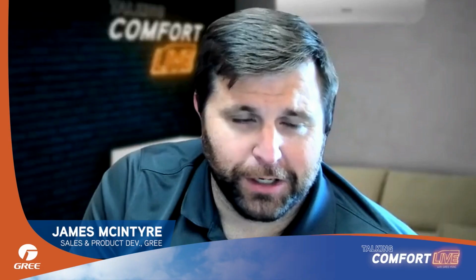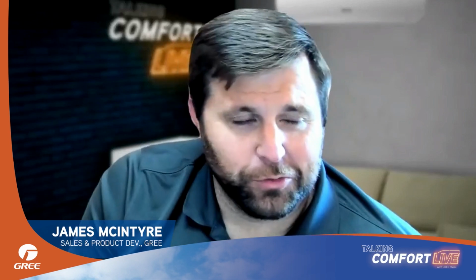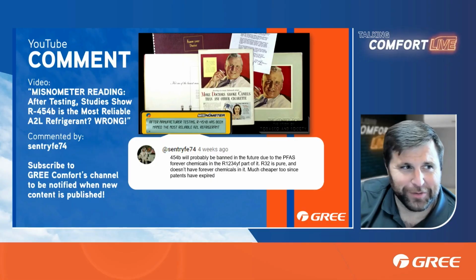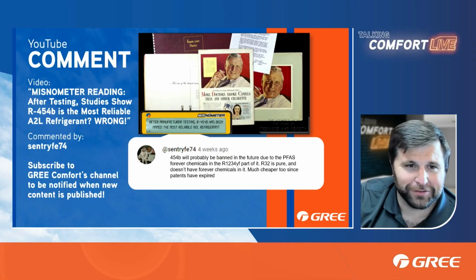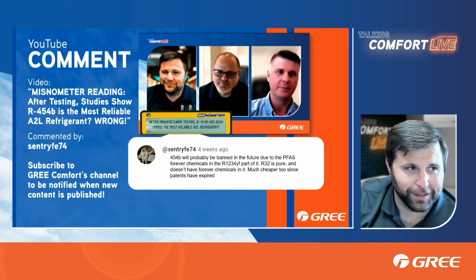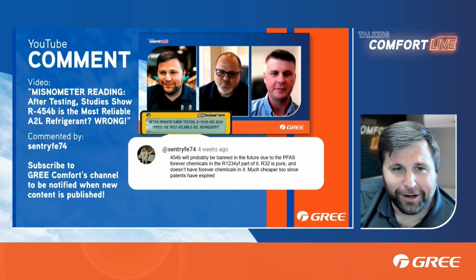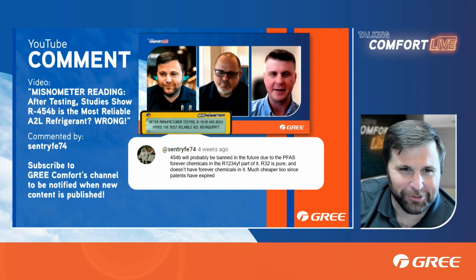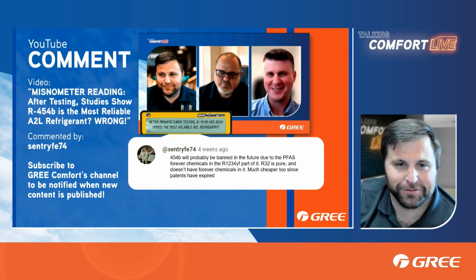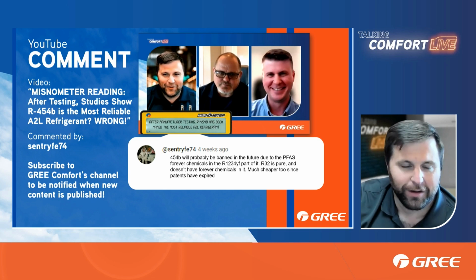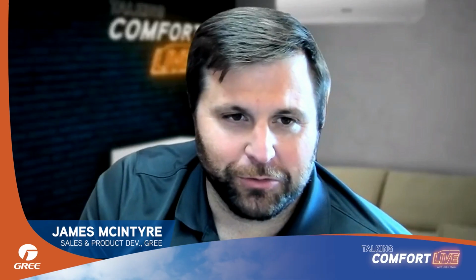That is true. Now, as far as the two refrigerants being offered currently, only one has been used for 15 years. Only one isn't a blend. Only one doesn't have active patents that somebody is getting paid on. It's being used globally currently, so there are many suppliers of R32, which keeps prices lower. R32 is used globally, and that's where most manufacturers from a global standpoint have already headed, or are already heading.